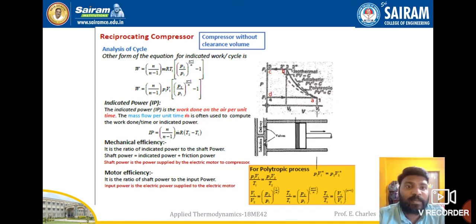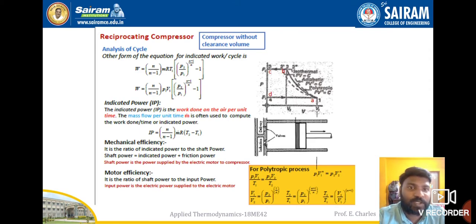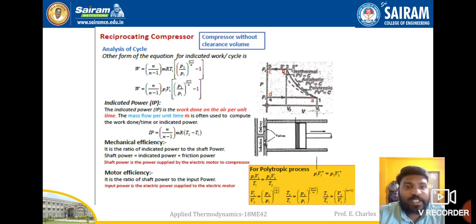In reciprocating compressors, indicated power will be less, whereas in IC engines indicated power is more — that is the key difference. Shaft power or brake power equals indicated power plus friction power. The shaft power is the power supplied by the electric motor to the compressor. Motor efficiency is the ratio of shaft power to input power, i.e., brake power divided by electric input power supplied to the electric motor.